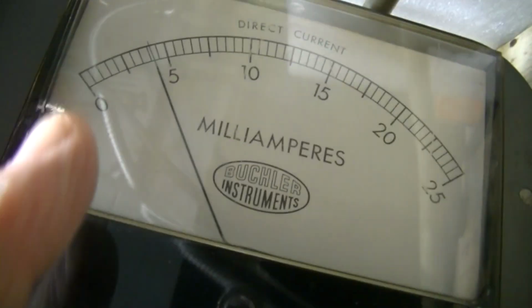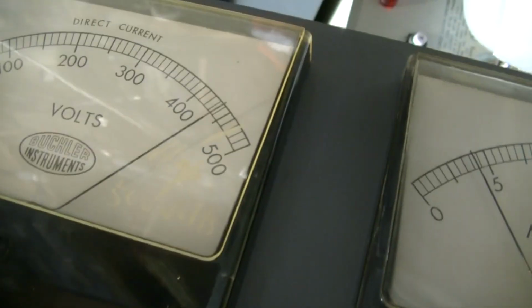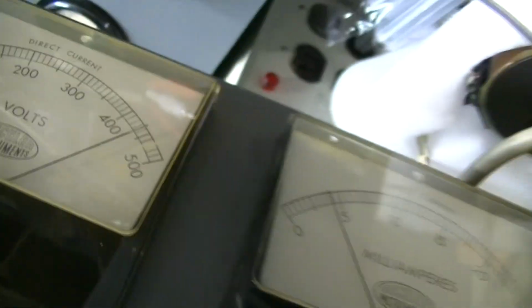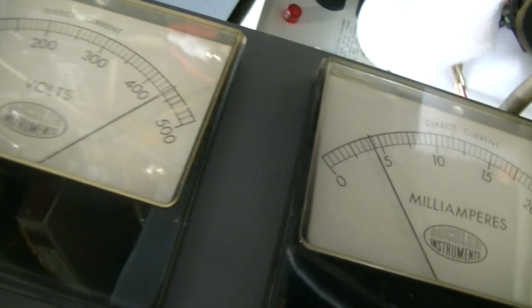Okay, well, we're getting 4 mils. Don't forget this thing's on the side. This meter doesn't seem to be affected by being on the side, but this one is. So we can't really go by the voltage there because we're reading over 400 volts, but like I say, it's because the meter's on the side, the whole unit's on the side.